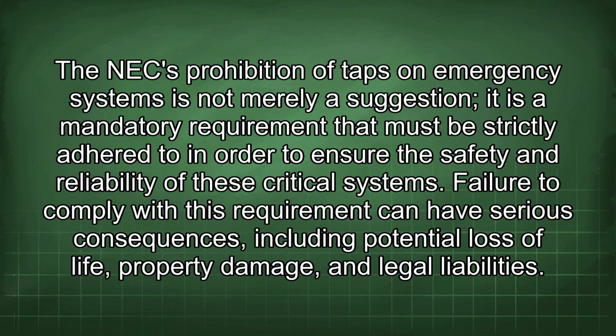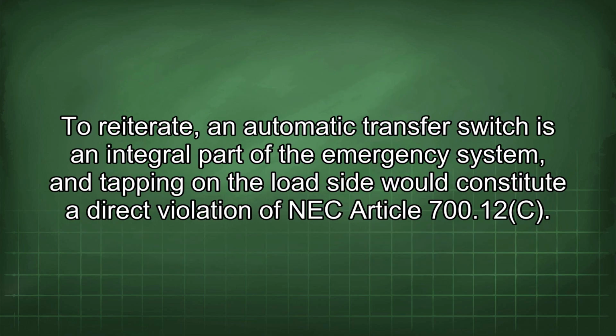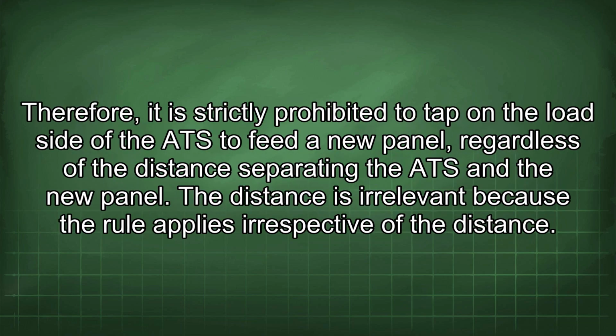The NEC prohibition of taps on emergency systems is not merely a suggestion, it is a mandatory requirement that must be strictly adhered to in order to ensure the safety and reliability of these critical systems. Failure to comply with this requirement can have serious consequences, including potential loss of life, property damage, and legal liabilities. To reiterate, an automatic transfer switch is an integral part of the emergency system, and tapping on the load side would constitute a direct violation of NEC Article 700.12(C). Therefore, it is strictly prohibited to tap on the load side of the ATS to feed a new panel, regardless of the distance separating the ATS and the new panel. The distance is irrelevant because the rule applies irrespective of the distance.